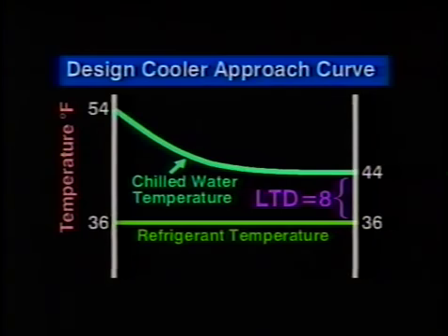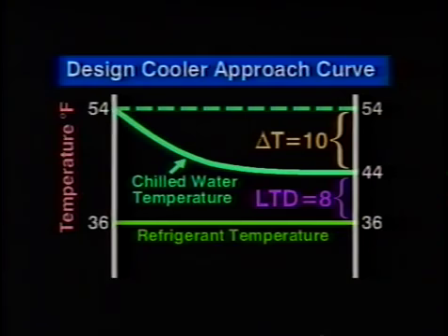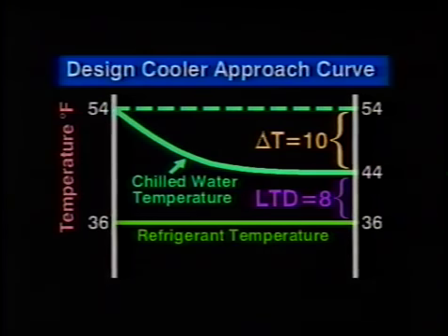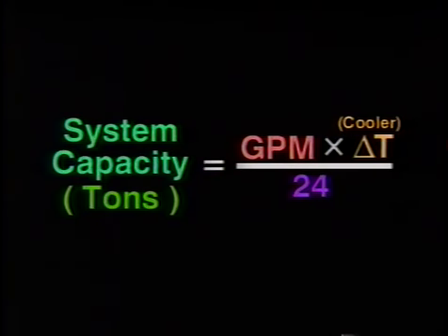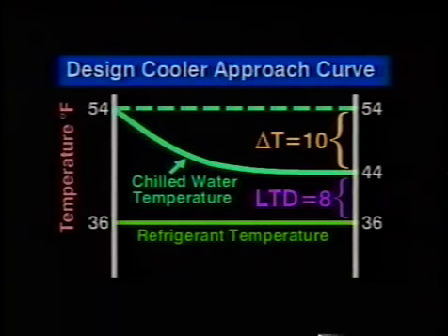The difference between the entering and leaving chilled water temperatures, delta T, along with the water flow rate, defines the total amount of heat transfer occurring. To refresh your memories, the system capacity in tons of refrigeration is equal to chilled water flow, GPM, times cooler delta T divided by 24. The delta T and the LTD are important and useful relationships in troubleshooting. Let's see how we can use these temperature relationships in troubleshooting some typical cooler problems.